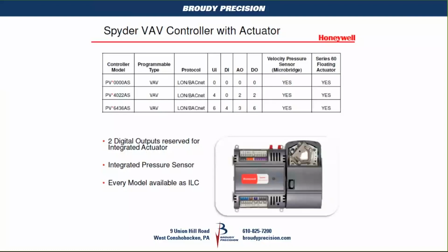And then if you have an application where you need a lot more I/O, they make the 6436AS. And again, you're missing 2 digital outputs which are dedicated for the actuator itself, the floating actuator. Power open, power close. All VAV controllers include the integrated pressure sensor, which is their Microbridge for velocity pressure. And everything that you see up here also comes in the BACnet flavor. So you're essentially looking at 6, not including the ILC, because every single one of these models comes in the ILC as well. So there's a good variety of controller models to match your application and keep your price point down as low as possible.